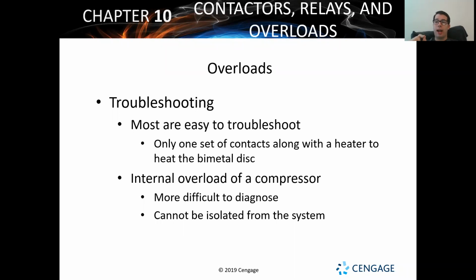Now, the difficult thing with an overload is to make sure that when you're troubleshooting it, you are looking at the problems. You're not just simply, oh, well, bad overload, replace the part. No, make sure that it's not having an error for a reason. Fuses will pop for a reason. Overloads will trip for a reason. There's either overheating, a system has got too much amperage going into it, or the system's building too great a magnetism or something like that. Whatever it might be, these are the issues that we have to look at.